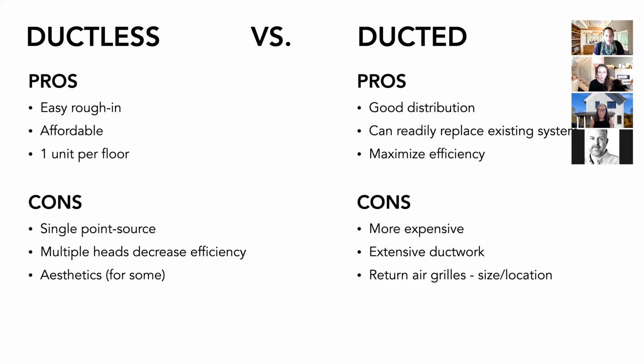Some of the drawbacks to ductless, though, might be that it is a single point source. So if you don't have an open living concept in your first floor, or if you have a lot of rooms broken up and you want to deliver even heat to each of the spaces or even cooling to each of the spaces, it's an important consideration to think whether that single head will suffice for your needs. Certainly, it will have the capacity to heat and cool the entirety of the space. If you have a space that you want to have the door closed all of the time, you might give consideration to either a backup source of heat or cooling for that space, or possibly a ducted system. You're not going to have a dramatic enough temperature drop with those separated out spaces to be uncomfortable, but you may see a noticeable difference between that space and the other if it's completely segregated out from the rest of the space. There are other things you can do besides backup heat or an additional head to mitigate that, vis-a-vis transfer fans or undercut doors to allow for air movement between spaces.